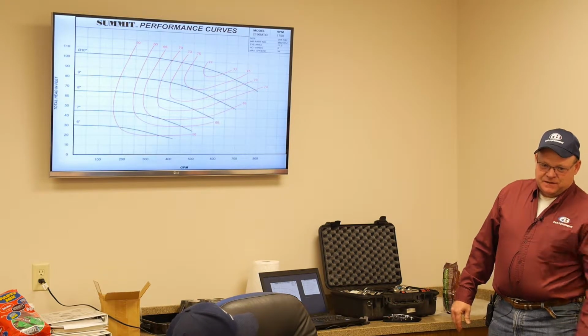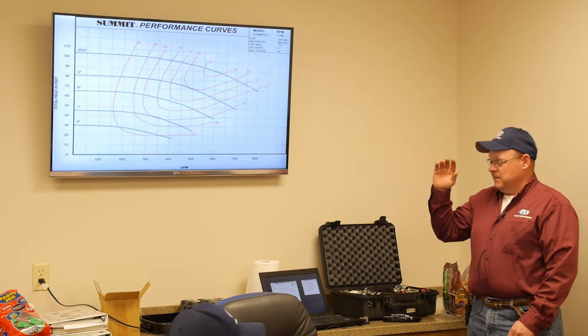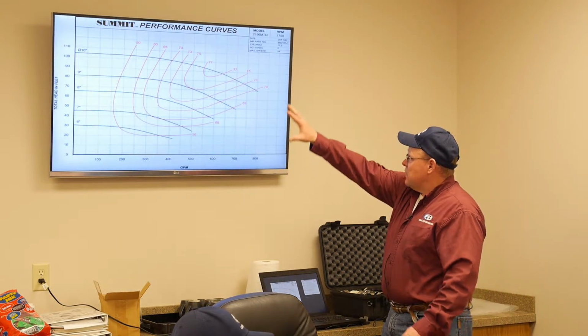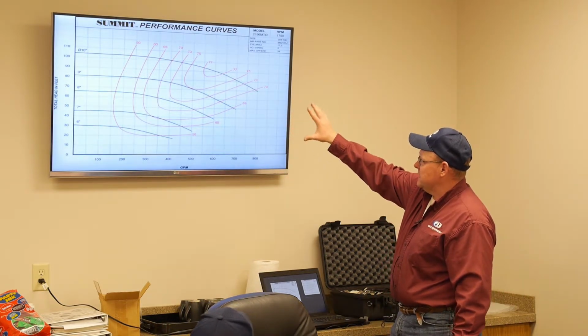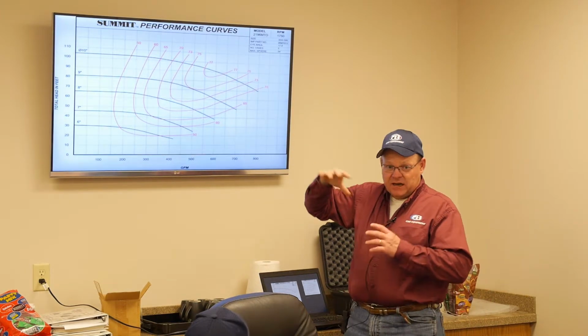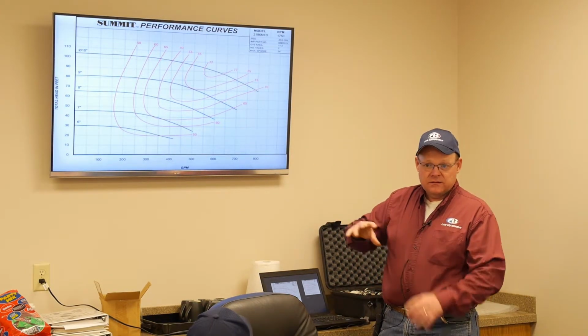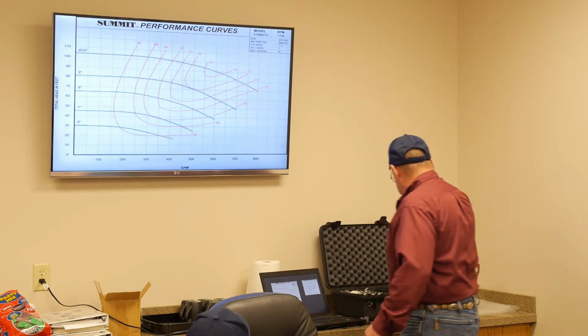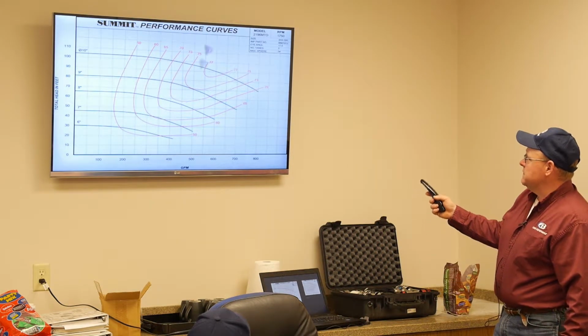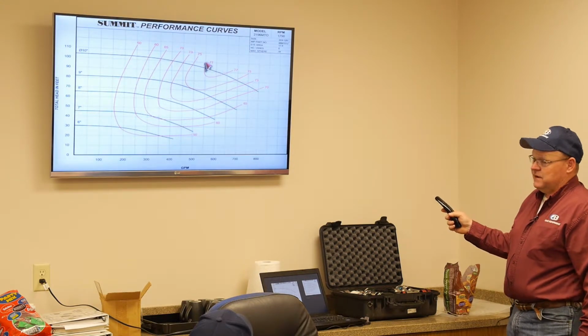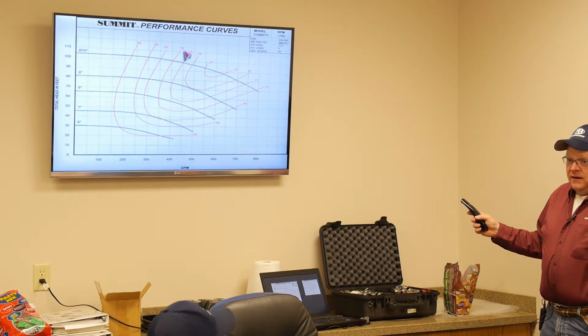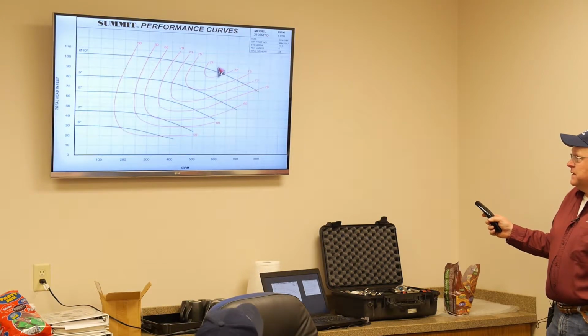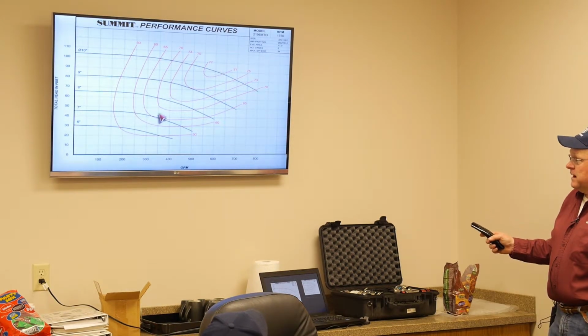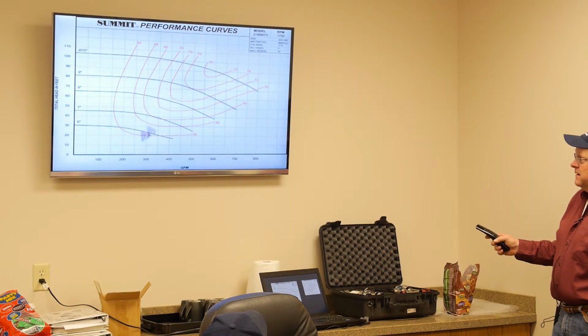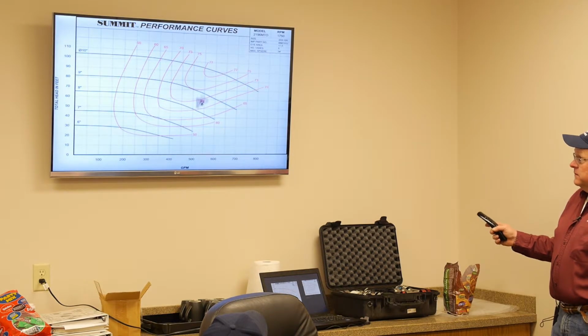BEP is the best efficiency point. The beep. So if these are all representative of efficiencies, that's what they represent. And this is what we call the eye of the curve, eye of the storm. This part right here, to get the best efficiency, would be right in here. 77% efficient. Okay, so if this is 77% efficient, you see how it kind of moves all the way down? So right in here, as we trim the impeller, is going to be our good.